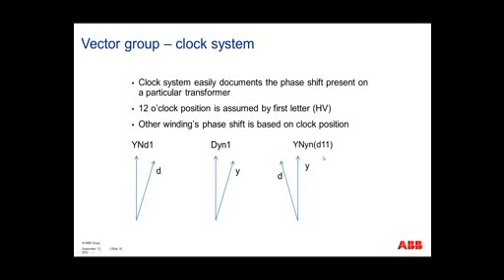The third example is a 3-winding transformer with a tertiary. We have a Wye-Wye delta connected transformer, where the Y side, high voltage, is at the 12 o'clock position. The low side is a Y connected transformer at the 12 o'clock position, which has no phase shift. And then the tertiary is at the 11 o'clock position, where it's shown here by the little d. This gives us that the tertiary now leads the high side and the low side by 30 degrees.